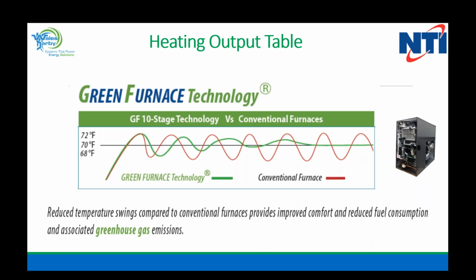On the very first slide, you've seen something on there. It said green furnace technology. And what does that mean? Well, what that means is we can actually reduce the temperature swings within the house based upon how the blower operates and senses stages and remembers its last cycle. So we can reduce the temperature swings within the home. Because of that, we reduce green emissions and so on, carbon footprint, and that's what allows us to qualify to call this a green furnace technology. And we basically smooth out that line, as you can see in the diagram. Green furnace technology would line right up with that 70-degree column with very, very little waves.